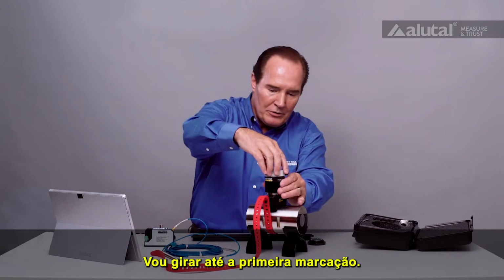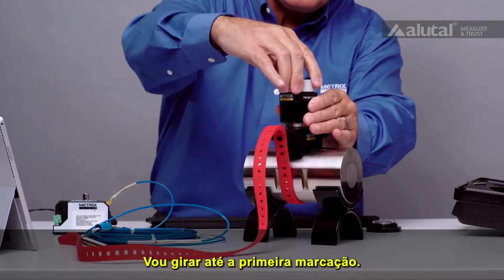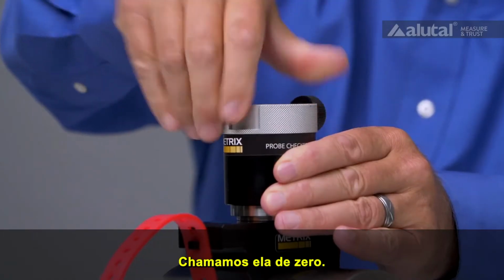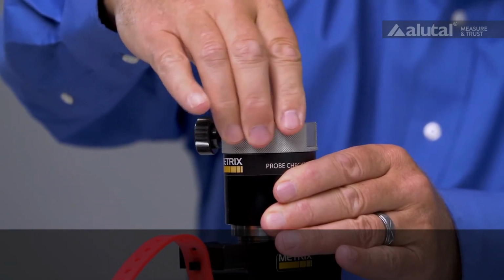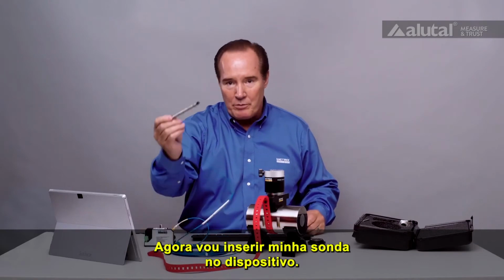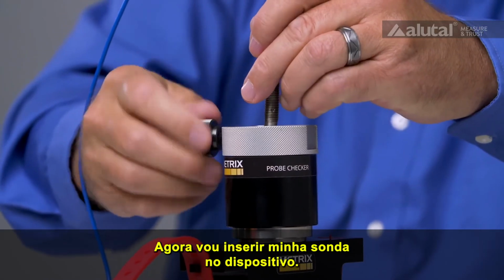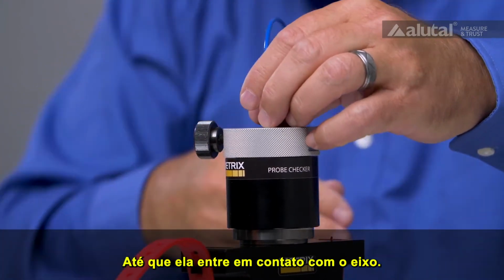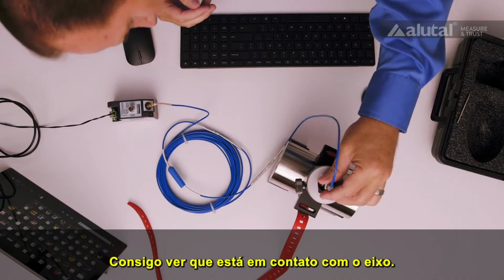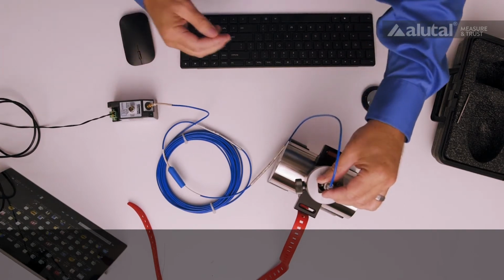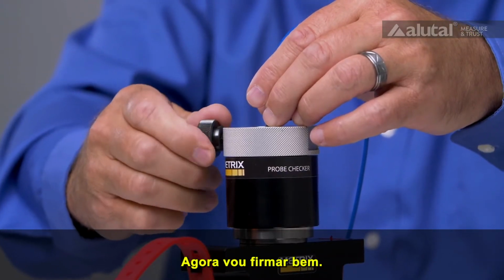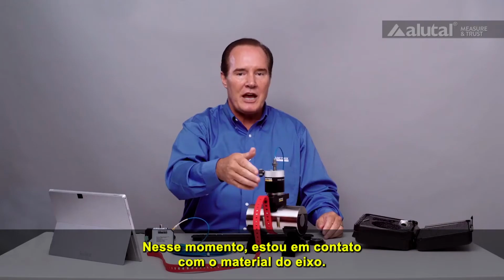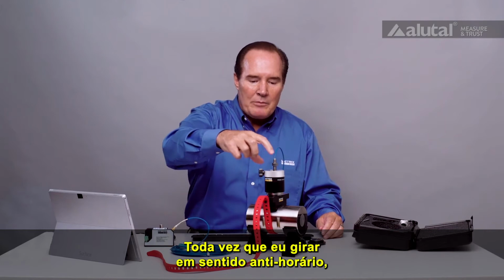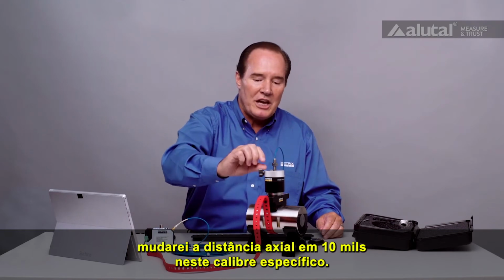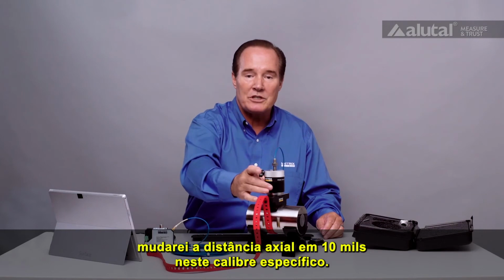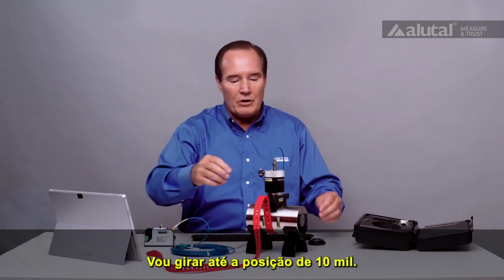Okay, so what I'm going to do is put it down to what would be considered the first marker, and we'll call that 0 right there. Then I'm going to insert my probe into the device, and I'm going to put it down until it contacts the shaft, and I can see that it's contacting the shaft right now. And then I'll go ahead and tighten this up. So right now I'm in contact with the shaft material. And now every time I move it counterclockwise, I'll be changing the axial distance by 10 mils for this particular calibrator. So we'll go ahead and go to the 10 mil position.